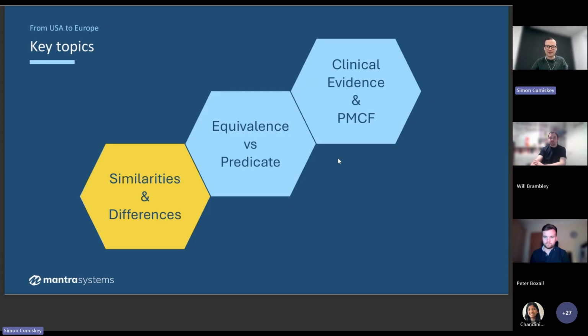And then the final difference is really on that overall approach to certifying products. In the FDA, it's broadly split by device risk classification as to whether a 510K or PMA or de novo route is appropriate, and with those come different requirements, whereas in the EU it's risk classes 1, 2A, 2B, 3. Regardless of the risk class, all of the requirements still apply.